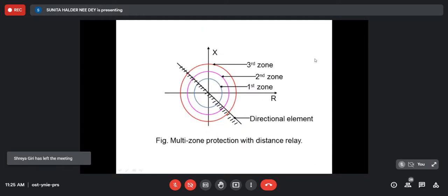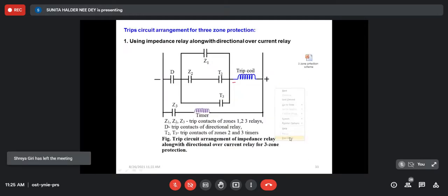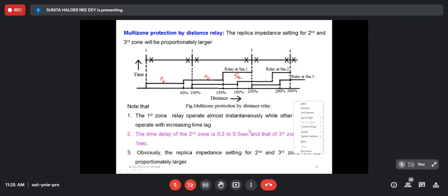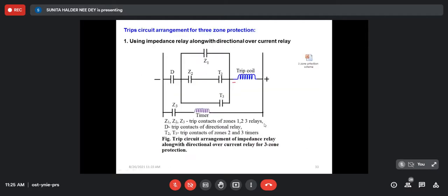So say we go to this figure. If we are assuming this relay in the zone 1, 2, right? Then zone 1, 2 will provide primary protection for the section 1, 2 up to 90%, secondary protection up to this 150%, then the third zone protection up to this 200%. Then how will it be? It will be controlled by the control circuit.